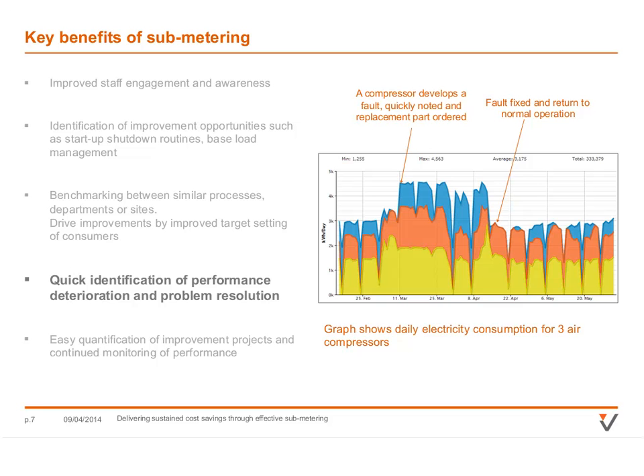This adds them all together and shows the 3 different compressors. You can see one basically developed a fault, which meant it was on all the time. I think a diaphragm might have developed a fault, and we could quickly spot there was a deterioration in performance, so a replacement part was able to be ordered quickly.